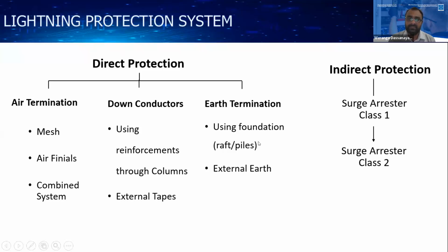Then earth termination means that the current from the down conductors has to be safely earthed to the ground. That system you are calling the earth termination system. It can be that there is a foundation or raft or piles in the building being used, or there may be an external earth. So when you are going to a building, you have to clearly note whether there is a lightning protection system installed in the building and what type it is, whether it was constructed with the building construction or installed after the construction of the building, then what the components are, and whether all these things are installed correctly.